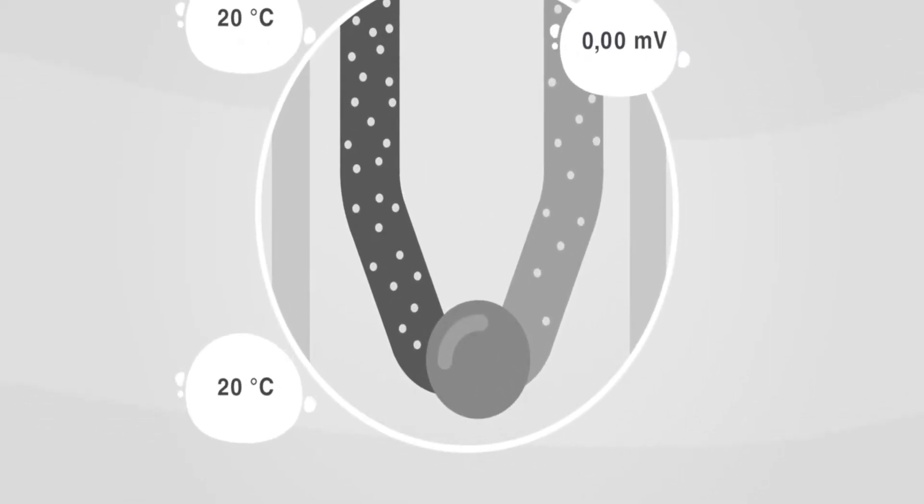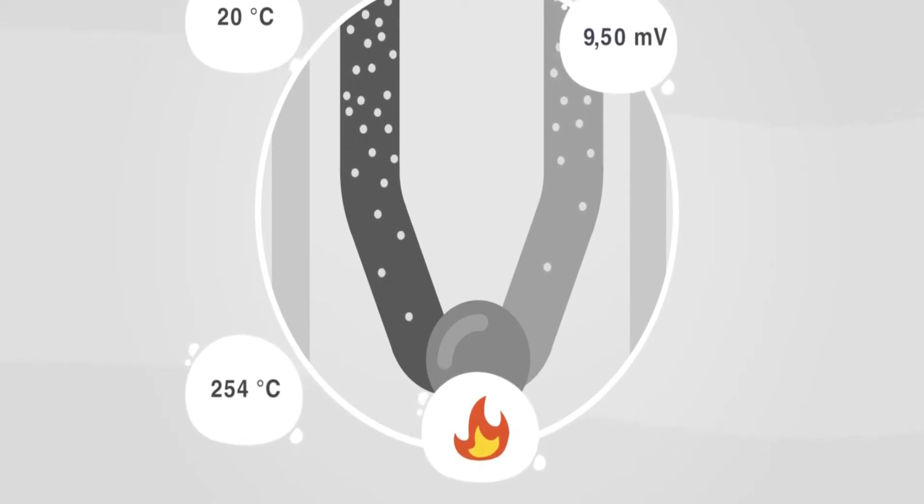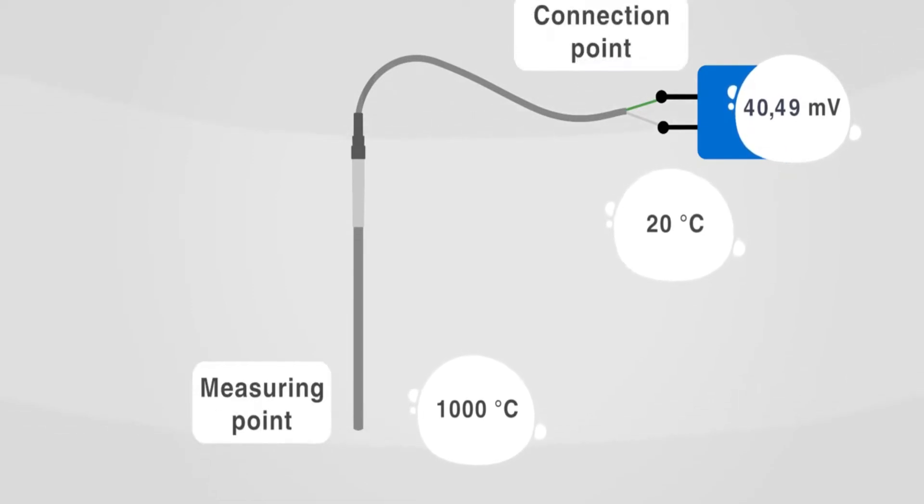When the temperature at the measuring point rises or drops, the electron density of each metal also changes. This altered electron density, i.e., the voltage, is measured at the wire ends. A thermocouple never measures the absolute temperature, but always the differential temperature between the measuring point and the connection point.